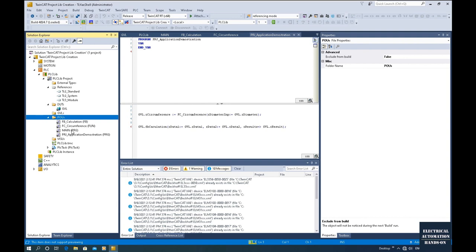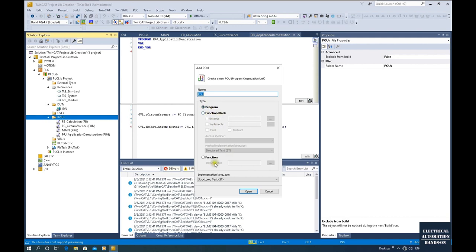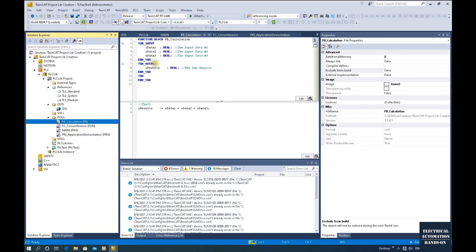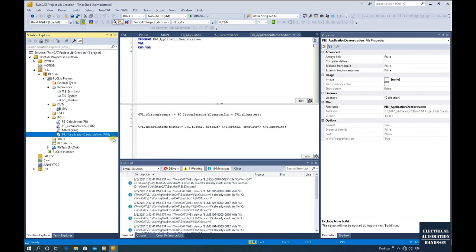I also highly recommend you do not create any code within the PRG (program). When we create a POU, we can create three styles: a program, a function block, or a function. If you create something as a program and export your code as a compiled sealed library, when you import it you cannot see the detail code inside. When we import the program code, you basically have no idea what it's doing. But for functions or function blocks, when you see those comments you know what the functionalities are. So keep your project clean — only functions and function blocks, without using the program.